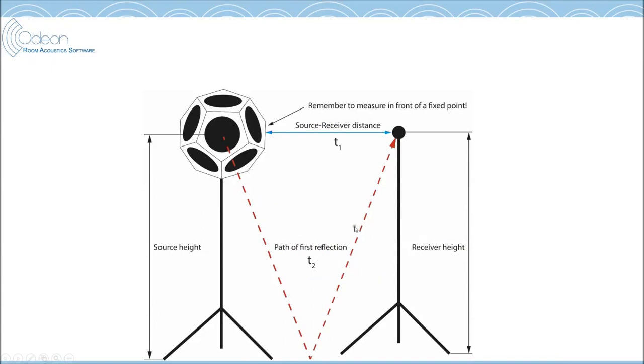The trick here is that we can gate away, so we can cut away the reflections from our measurements, so it will actually be identical whether you are on site having reflections from the floor, or you are in the reverberation chamber, or if you are doing an anechoic calibration instead and you are in an anechoic situation. So we cut away any reflections and only have the direct sound. We don't care that we are in the near field region of the source, because this is just an offset. So if it's the same gated response we have in the calibration setup as in the in-situ calibration setup, then we don't care if it's near-field conditions. It's just an offset we are deriving, and we gate appropriately.